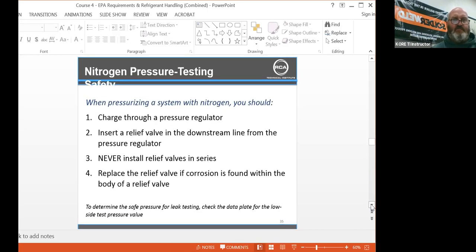When pressurizing the system with nitrogen, you should charge through a pressure regulator. Insert a pressure relief valve in the downstream line from the pressure regulator. Never install relief valves in series. You don't want one blowing into the next one. Replace the relief valve if corrosion is found within the body of a relief valve. To determine the safe pressure for leak testing, check the data plate for the low side test pressure value. So again, I'll look at an evap coil and see what the test pressure rating is, because I don't want to blow an evap coil in a market case or in a Maverick if I've exceeded the test pressure of that coil.